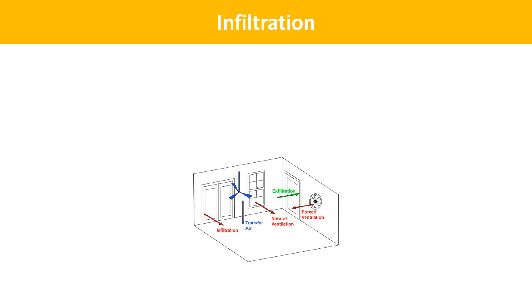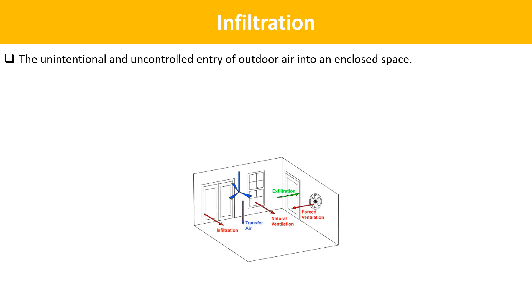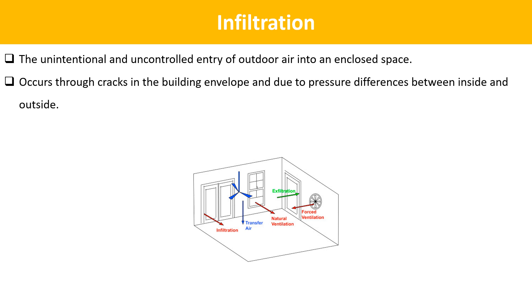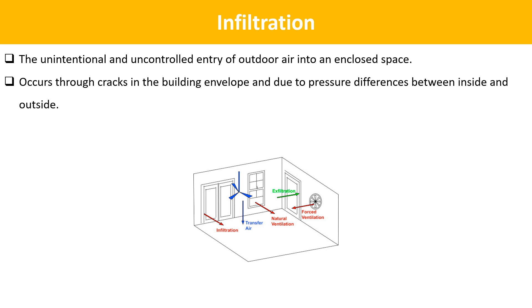The next term is Infiltration. The unintentional and uncontrolled entry of outdoor air into an enclosed space is called infiltration air. Infiltration occurs through cracks in the building envelope and due to pressure differences between inside and outside. Infiltration rates vary throughout the year and are greater in winter when the temperature difference between inside and outside is greater.